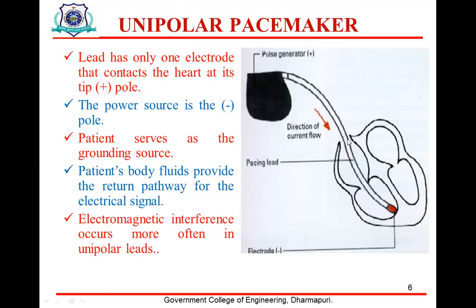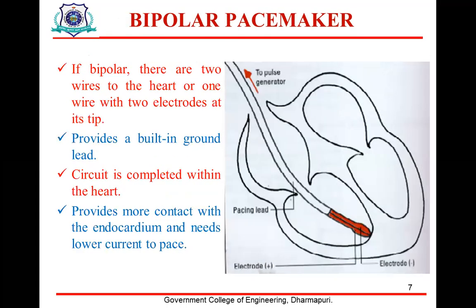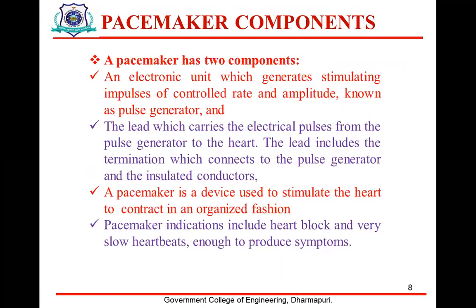Another way of classification is whether it is a unipolar pacemaker or a bipolar pacemaker. For a unipolar pacemaker, the lead has only one electrode, which contacts the heart at its tip, the positive pole. The power source is the negative pole. The patient acts as a grounding source. The patient's body fluids provide the return pathway for the electrical signal. Electromagnetic interference occurs more often in unipolar leads. For bipolar, there are two wires to the heart or one wire with two electrodes at its tip. It provides a built-in ground lead. The circuit is completed within the heart itself. It provides more contact with the endocardium and needs lower current to pace.